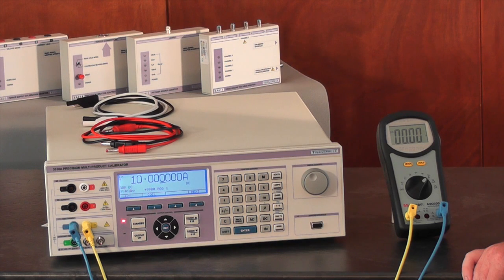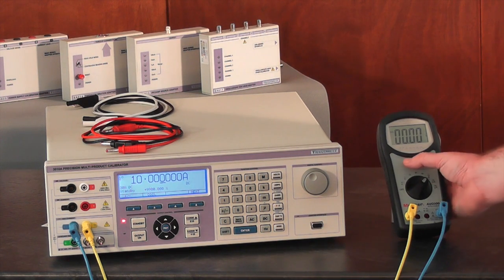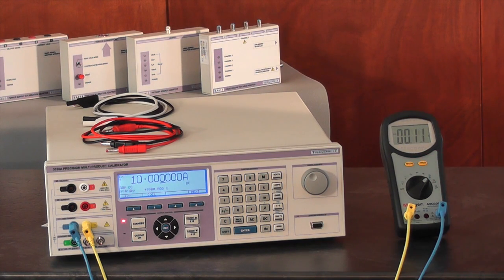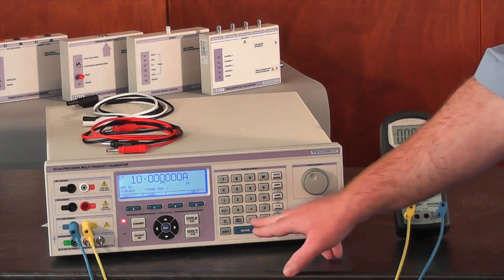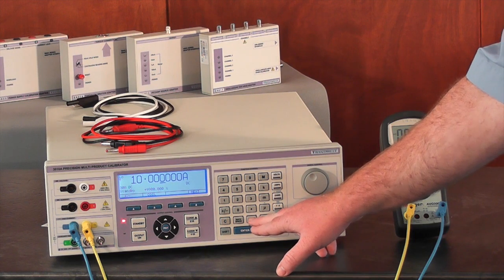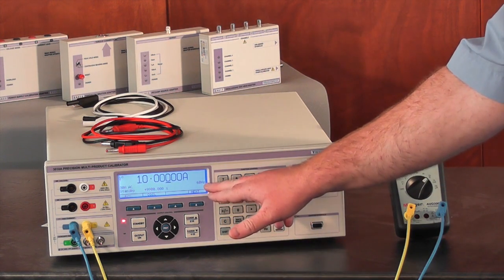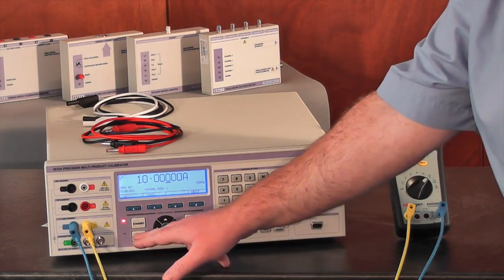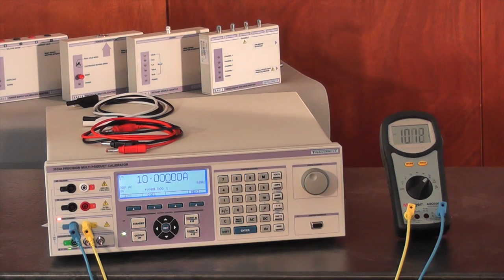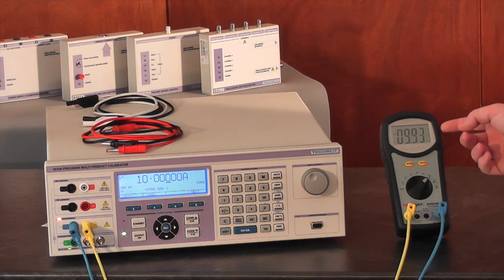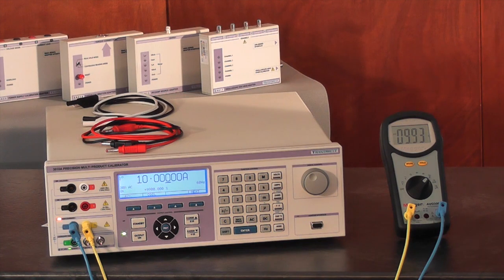Measuring high AC current follows the same procedure as before: switching the multimeter into AC mode, switching the calibrator into AC mode, verifying the frequency, and pressing output on. Once again, we can take a value from the multimeter.